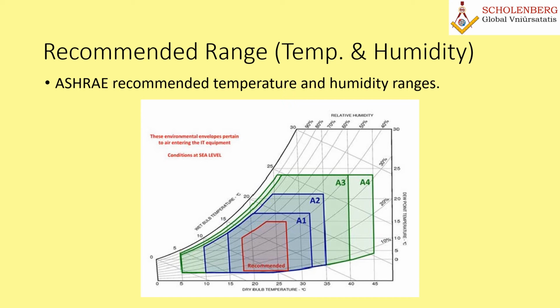The recommended and allowable ranges for each datacom equipment class are given below. The allowable environmental ranges for the four datacom equipment classes are here. First is class A1. Class A1 is typically a datacom room with tightly controlled environmental parameters, including dew point, temperature, and relative humidity, for mission critical operations. Products typically designed for this environment are enterprise servers and storage products. This you will find very commonly.